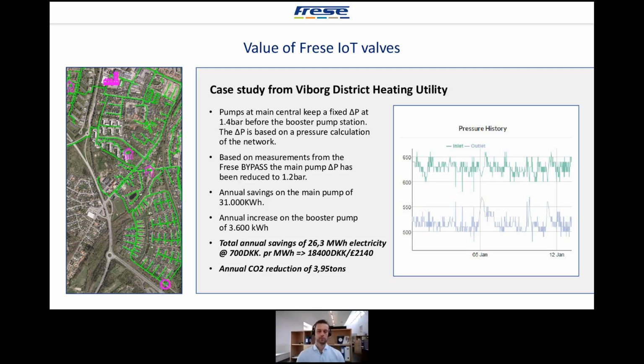But when they started to verify what was actually going on, they soon realized that they were running their pumps too hard. And running their pumps too hard is, of course, a costly affair, but they didn't know because they didn't have any complaints. Now they have the facts to check up on it and actually do something about it. So by tweaking a little bit on their pump operation, they were able to save more than 26 megawatt hours of electricity annually. And that actually leads to a reduction of almost 4 tons of CO2 per year. This was all just done due to some new knowledge about their pressure throughout the system. So it was a very, very small investment to gain quite a lot of benefit.